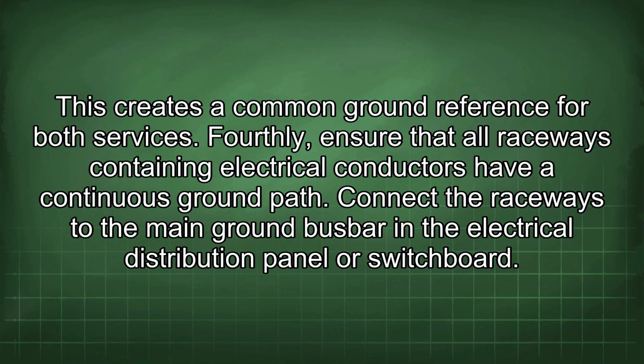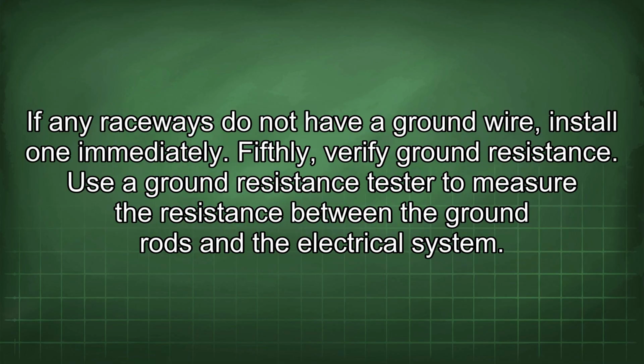Fourthly, ensure that all raceways containing electrical conductors have a continuous ground path. Connect the raceways to the main ground busbar in the electrical distribution panel or switchboard. If any raceways do not have a ground wire, install one immediately.